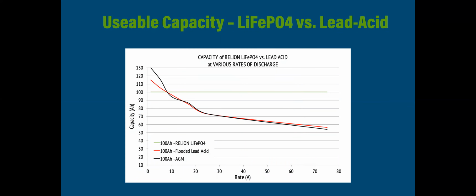So we recommend a Peukert coefficient of 1, which represents zero inefficiency, or the battery being 100% efficient. There is documentation suggesting you might put in 1.02 to 1.05 for a lithium battery, and that's really to accommodate for really high rate loads when you get up around 3 or 4 C, which most people don't encounter. So you'd really be safe using a Peukert number between 1 and 1.05—we'll leave it to your discretion to pick.